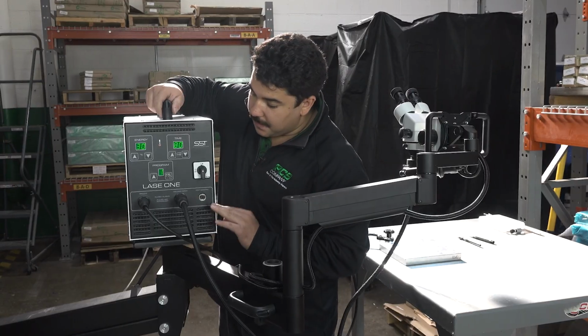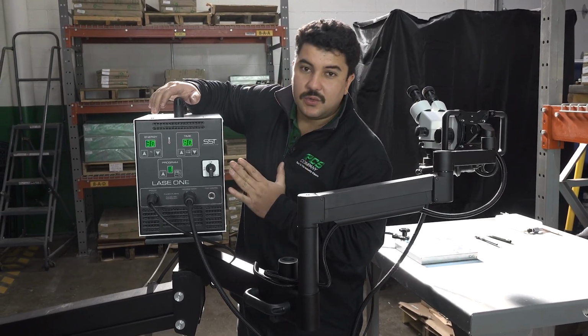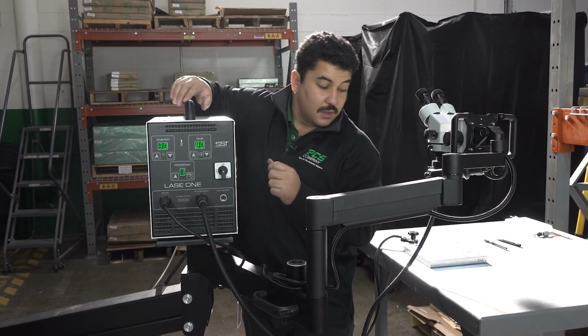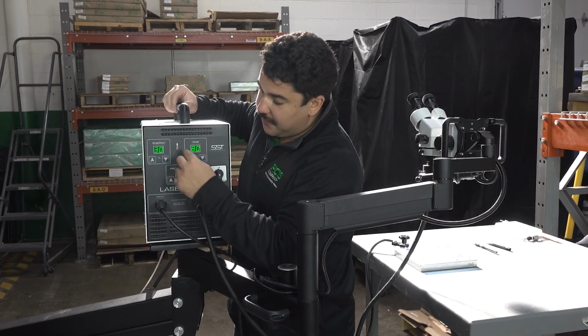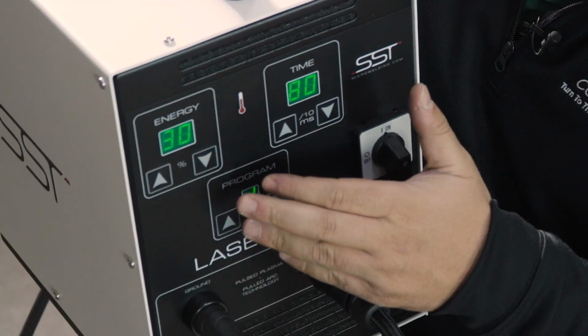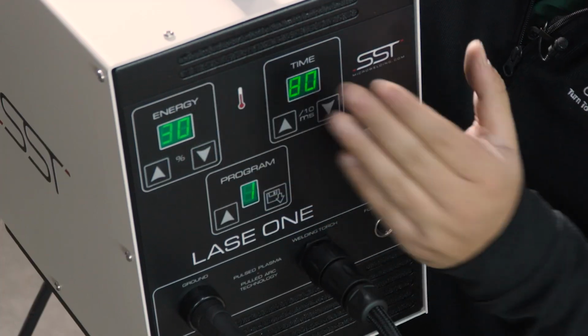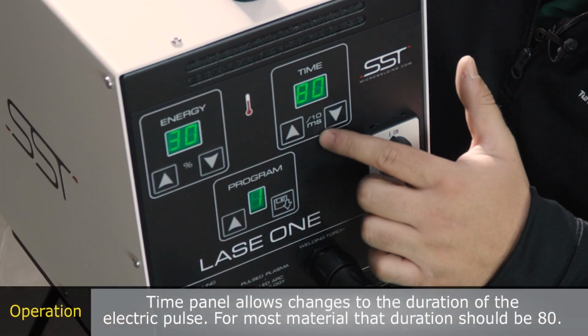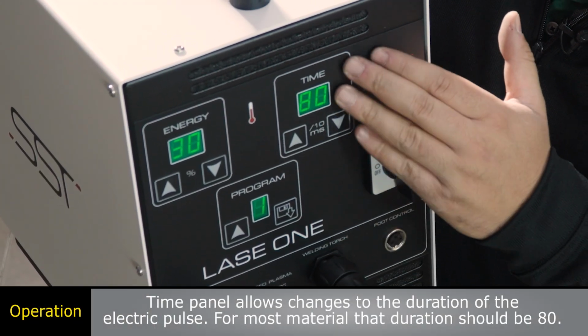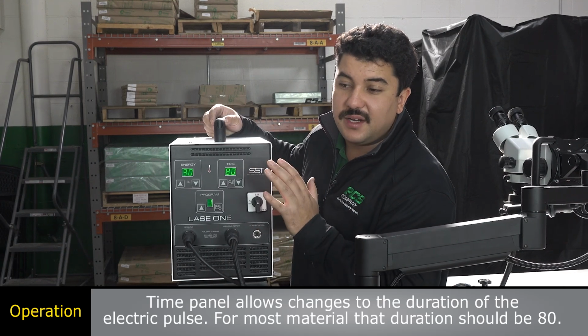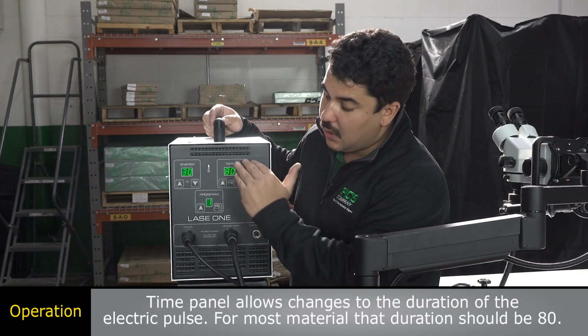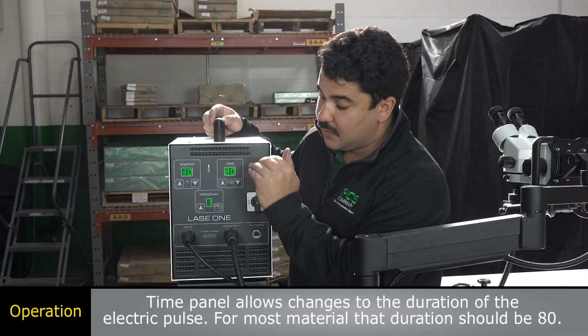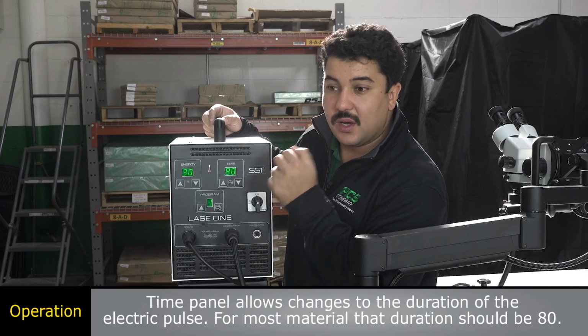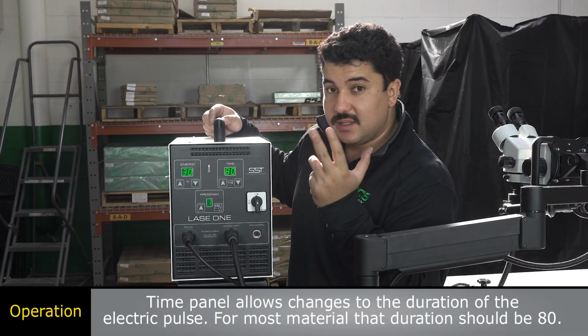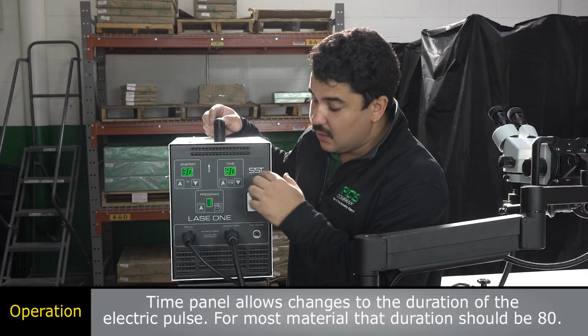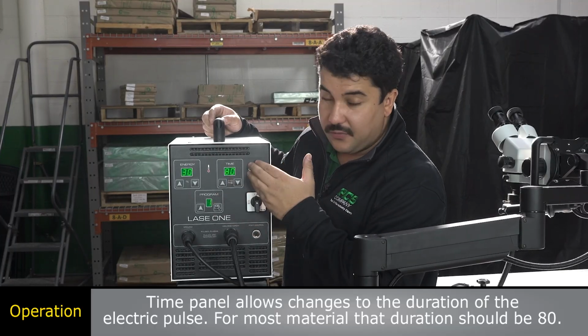So here I will explain to you how the machine works. It's really simple. We have 3 settings: the program, the time, and the energy. The time is the duration of the sparks. It will be the same for all materials except aluminum. Well, we decrease it a little bit to 60. For all materials, copper, bronze, stainless steel, titanium, nickel, you can stay at 80. So you can forget these settings.